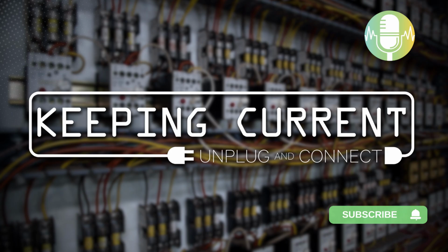Going back to another situation, it was a utility plant. They burned down the entire section of 4160 GE Magnablast gear, all because somebody rolled the interlock wrong. They racked in a GE Magnablast breaker, closed it, and it tried to start the motor. Additionally, at this utility plant, the polarity on the relay was rolled—it was an original GEIC relay—and it took out the transformer differential out in the yard.